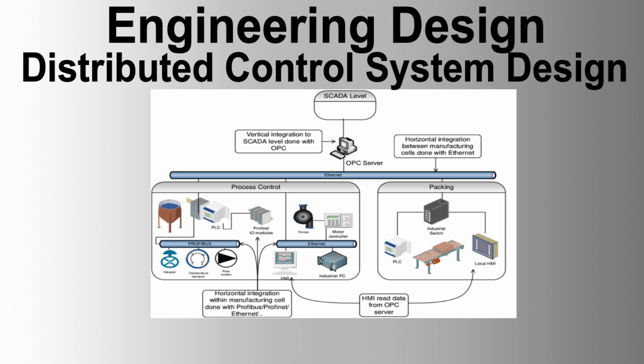3. The DCS will provide centralized control and monitoring of all process operations, including alarm and event monitoring, sequence control, startup, shutdown of individual items of plant, and interface with other control and shutdown systems. All machinery and process packages will be serially linked to the DCS for full control and status monitoring.